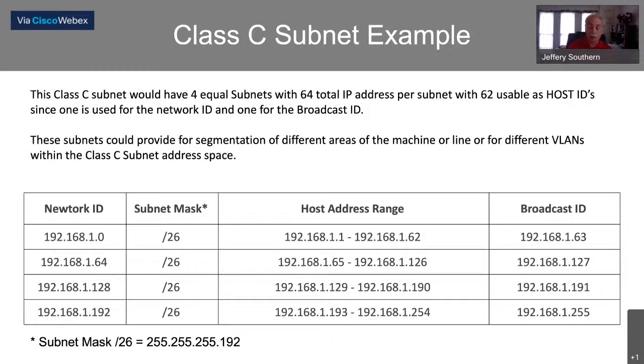And the reason we did that is because we didn't know what it was for. I mean, that was typical controls. We just knew it worked if you set it that way. But now with the concept of needing larger networks and more resilient networks and proper segmentation, we need the ability to allow data from the outside, the SCADA world or the IT world, to cross boundaries and read data from, say, a processor on your process line. One of the most common ways that's done today is using a NAT device. Well, one of the requirements of a NAT, or even a router, is that on any given subnet, it have a gateway address.